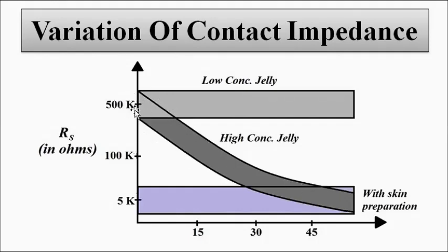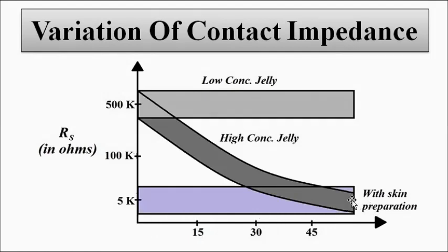For the high concentration jelly, initially the impedance is around 500 kilo-ohms, but then it decreases gradually and at around 60 minutes it reaches approximately 5000 ohms. For the skin preparation or skin abrasion case, the impedance is constant right from t equals zero and remains at 5000 ohms for the entire duration of one hour or more. So the low concentration jelly has a constant but high contact impedance, the skin-prepared case has a constant low impedance, and the high concentration jelly starts high then decreases gradually to 5000 ohms.